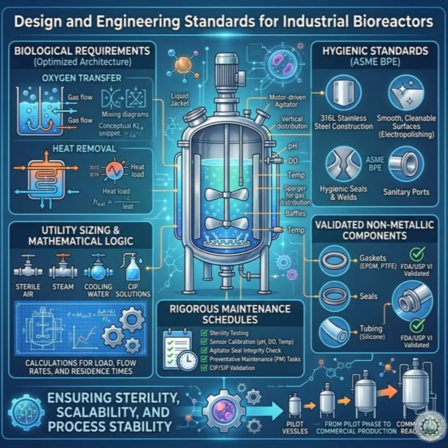Let's ground that in their specific example. Right, they assume a 25 kilowatt heat load in a 1,000-liter tank. And they stipulate that the cooling water entering the jacket surrounding the tank is only allowed to warm up by 5 degrees Kelvin before it has to cycle out, just to keep the internal temperature perfectly stable. Okay, so what's the result? When you run that math, you need about 1.2 kilograms of water flowing through the jacket every single second.